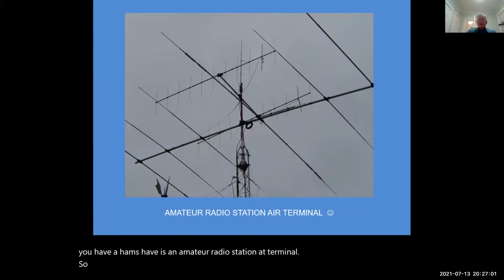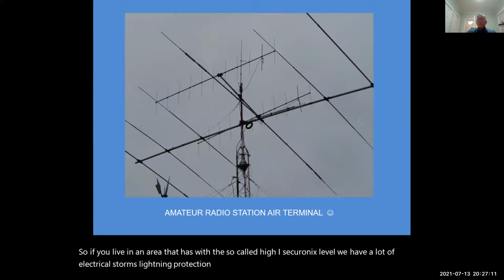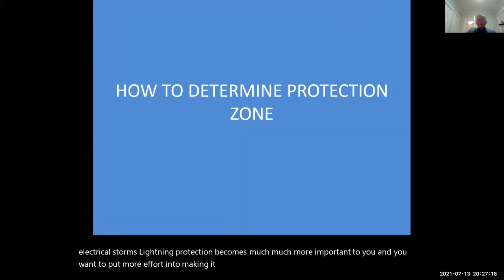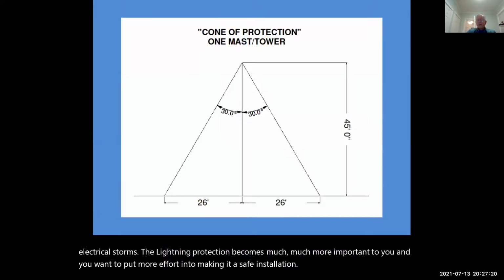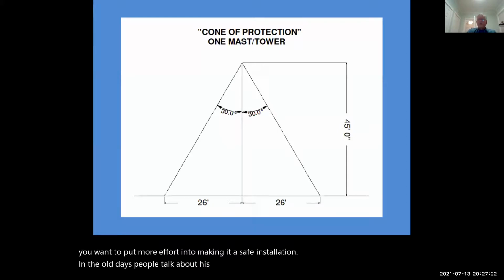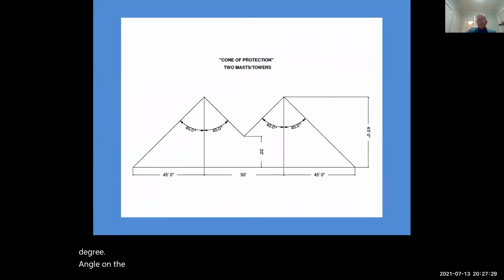If you live in an area that has a high isokeraunic level, where we have a lot of electrical storms, the lightning protection becomes much, much more important to you. And you want to put more effort into making it a safe installation. In the old days, people talked about the zone of protection, the cone of protection, either a 30-degree angle on the cone, or if you had multiple structures there. And it's been found not to be very accurate.